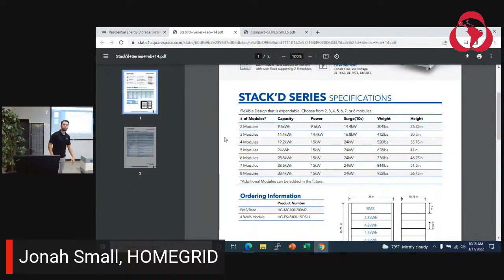Hey, Jonathan, one question. You mentioned a single battery or a single stack can get 15 kilowatt continuous. But then I heard you need 3 modules to get 14.8. Yeah, so at 2 modules, you can see on the spec sheet here, the continuous is 9.6 because it's only 9.6 kilowatt hours. It's a small battery at that point. So as soon as you step up to 3 modules, it goes up to 14.4. And then if you do 4 modules, we can do 15.